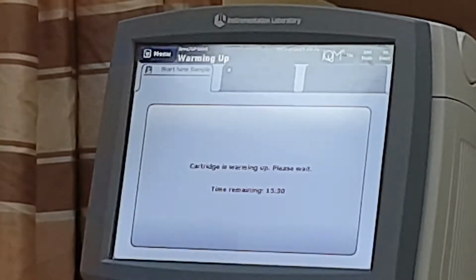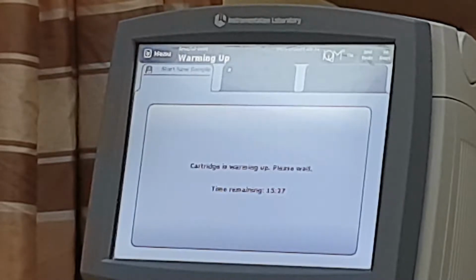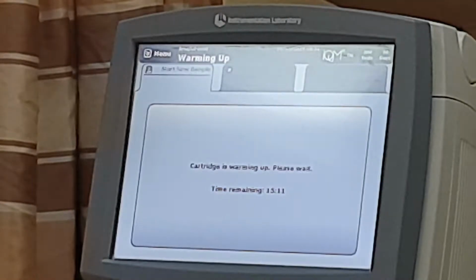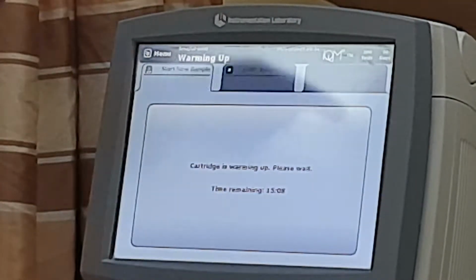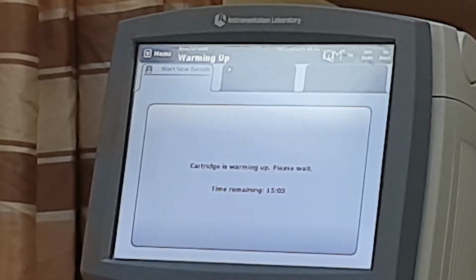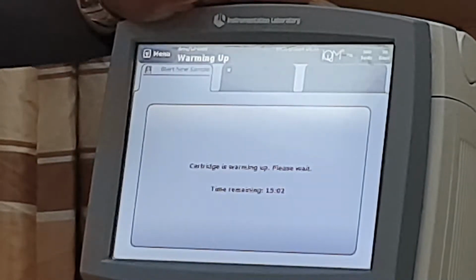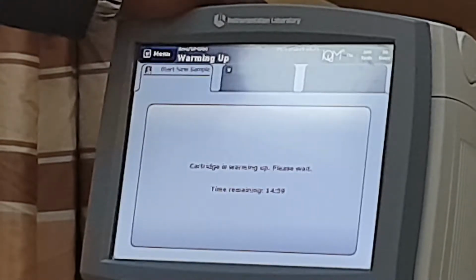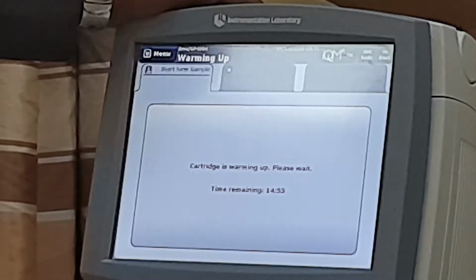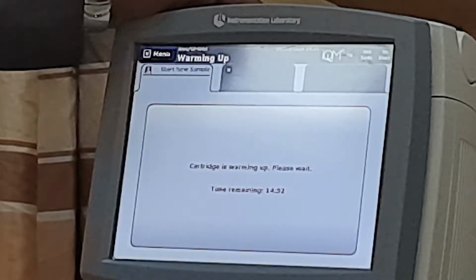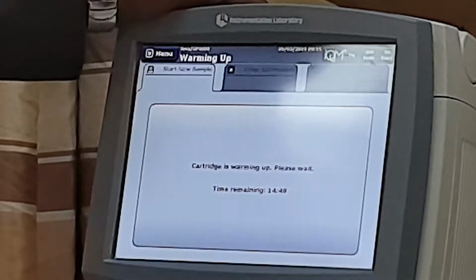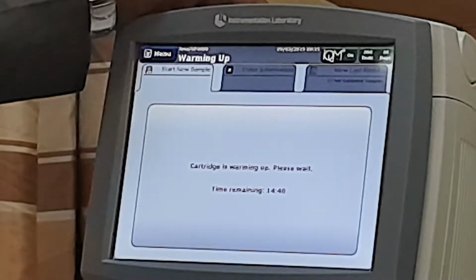Secondly, if you want to run a sample, the steps are very easy. We just check which type of sample you want to run, whether ABG, VBG, or even capillary, and select it. We will do it together as practice, inshallah. Then we press go. The needle will go down, then we insert our syringe. Press OK to aspirate. Then you remove the sample and enter the information for that sample. That's all. You will get the result within 19 seconds. The volume.